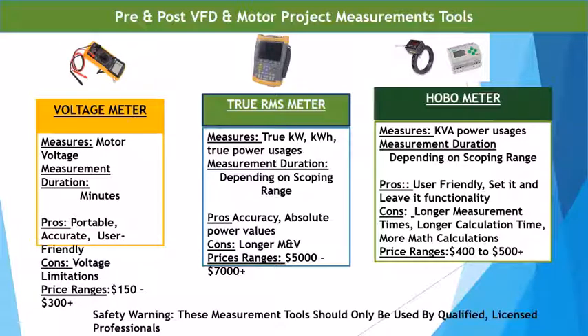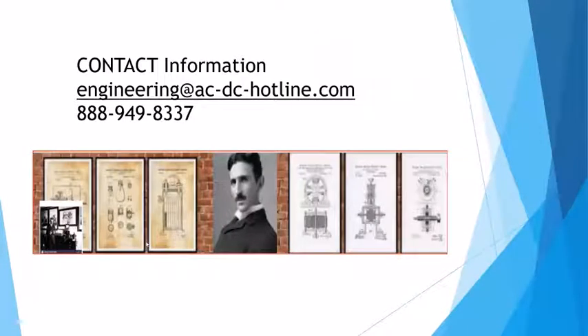So this is a little bit on some of the metering that's out there. You've got voltage meters, the true RMS Fluke equipment. There are some other manufacturers that make this also. I'm not promoting just one brand, but this was one that I used for a number of years and found very good success. And then there are what they call hobo meters. They allow you to stick it in and read things over time. They really don't give you real accurate values, but it does give you time slots of how often and what the motor is actually truly being used over time. So when you're doing your power efficiency calculations.